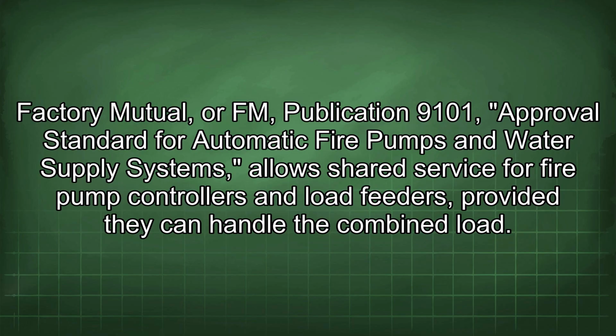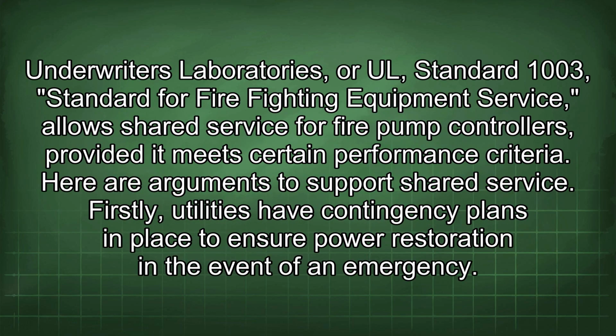Factory Mutual, or FM, Publication 9101, Approval Standard for Automatic Fire Pumps and Water Supply Systems, allows shared service for fire pump controllers and load feeders, provided they can handle the combined load. Underwriters Laboratories, or UL, Standard 1003, Standard for Firefighting Equipment Service, allows shared service for fire pump controllers, provided it meets certain performance criteria. Here are arguments to support shared service.